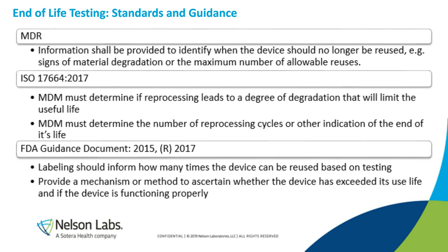The ISO document specifies that the medical device manufacturer must determine if reprocessing leads to a degree of degradation that will limit the useful life. Medical device manufacturers must determine the number of reprocessing cycles or other indication of the end of its life. And then the FDA document has very similar verbiage as the ISO document does. Now the issue with this is that currently without a unique device identifier, it is very difficult for healthcare facilities to count the number of reprocessing cycles or uses of those devices.